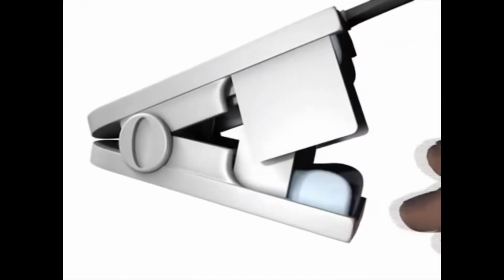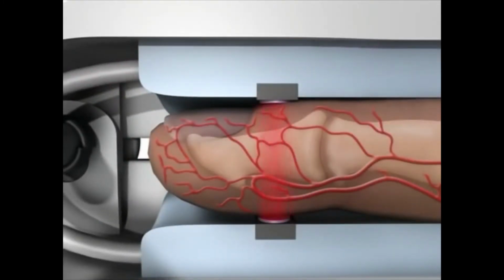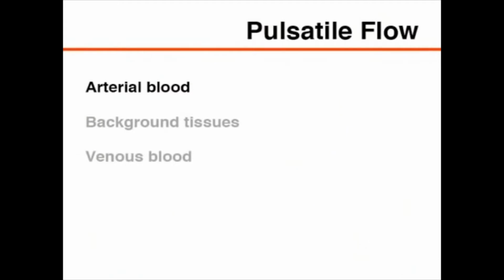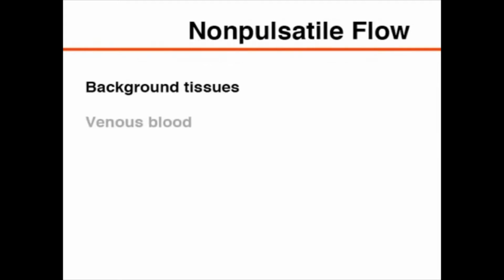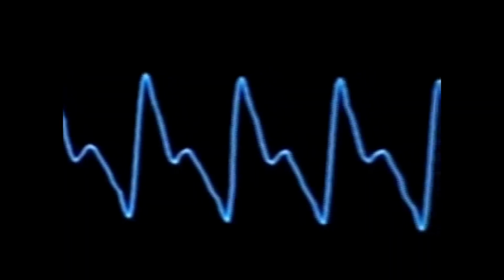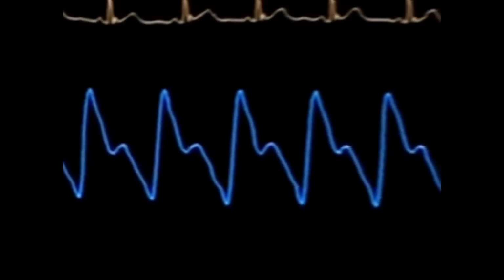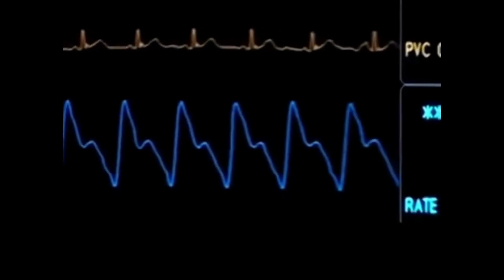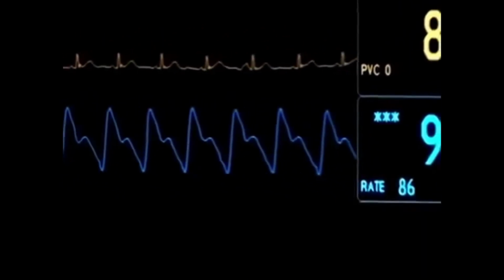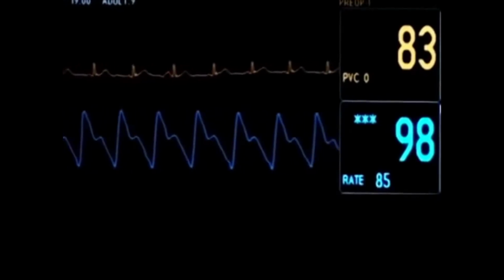The probe is positioned so that the photodetector and light-emitting diodes face each other, with layers of tissue between them. The light-emitting diodes turn on and off several hundred times per second to record the light absorption during pulsatile and non-pulsatile flow. During pulsatile flow, the light absorption of arterial blood, background tissues, and venous blood is detected. During non-pulsatile flow, only the light absorption of background tissues and venous blood is detected. The microprocessing unit compares the light absorption during pulsatile and non-pulsatile flow to isolate the light absorption of arterial blood and thus determine the arterial blood oxygen saturation.